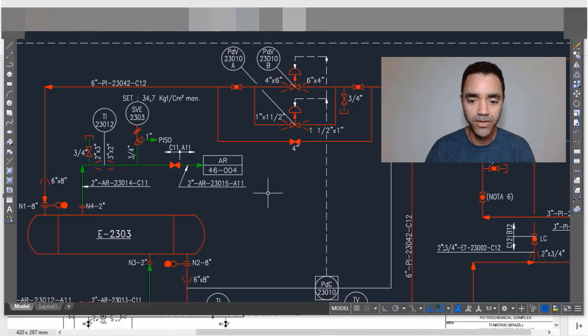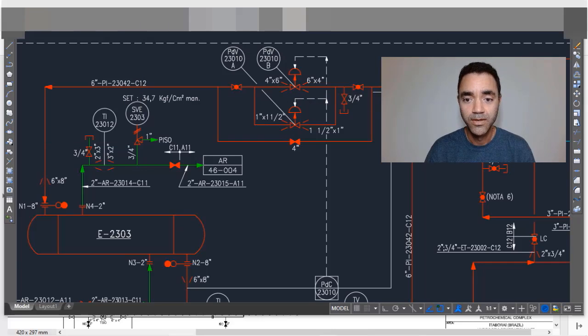In this case, what we have here is a controller and pressure differential valves to control the differential pressure between what is going in upstream of the heat exchanger and going out downstream of the heat exchanger. So we have the PDC, that means pressure differential controller. It takes a tap at the discharge of the heat exchanger and at the inlet of the control valves. This measurement is sent to a PLC also, and the output of the PLC goes to two control valves.